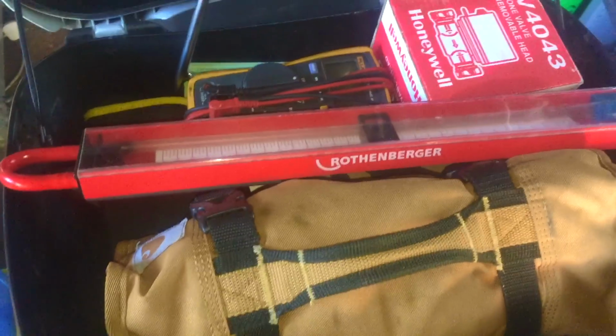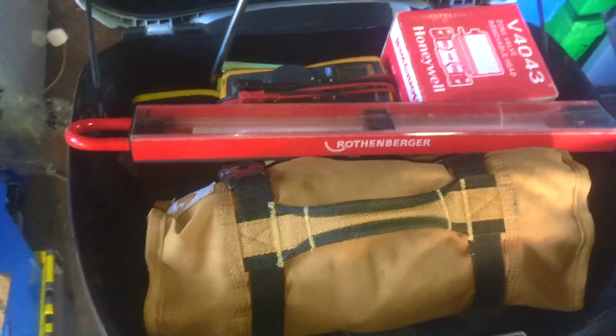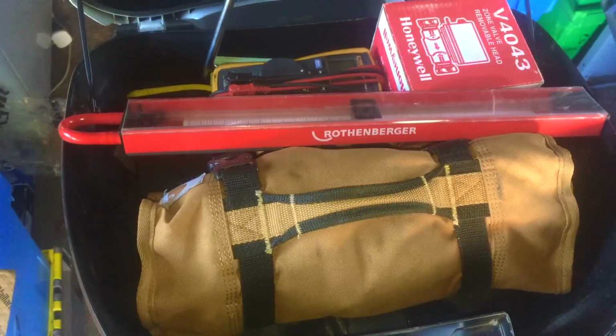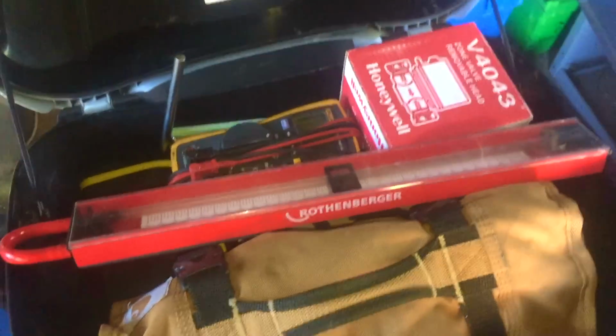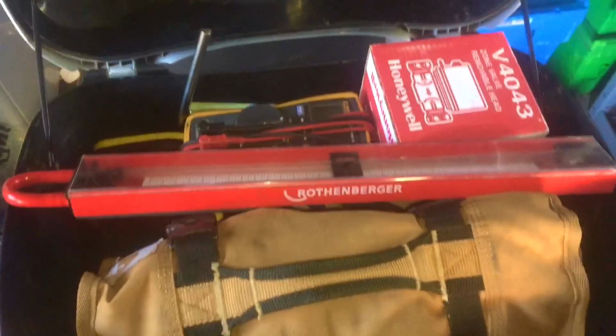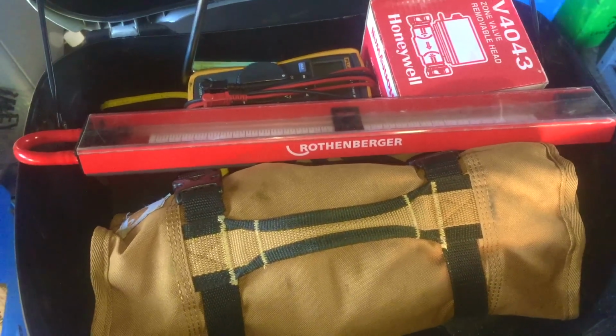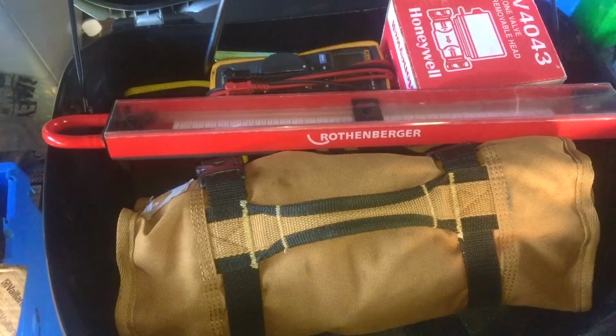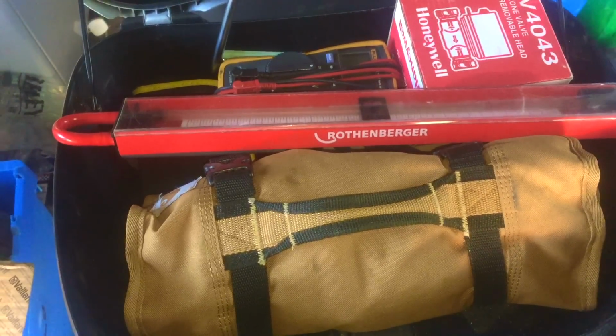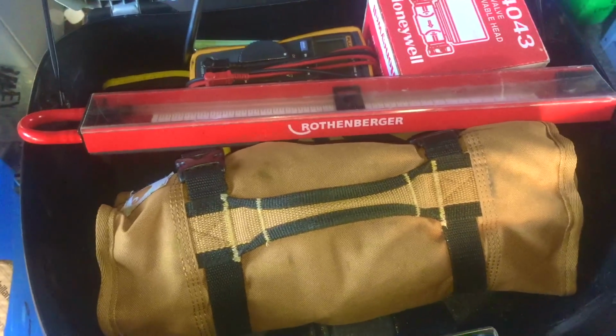Okay, so the wiring job and testing I did in the last video on the system with the 2 ports, I've had a recall on that. The lady phoned me to say she could hear the boiler was on, but the flame wasn't on, according to the lady, but the pump was running and it didn't stop even though everything was turned off.